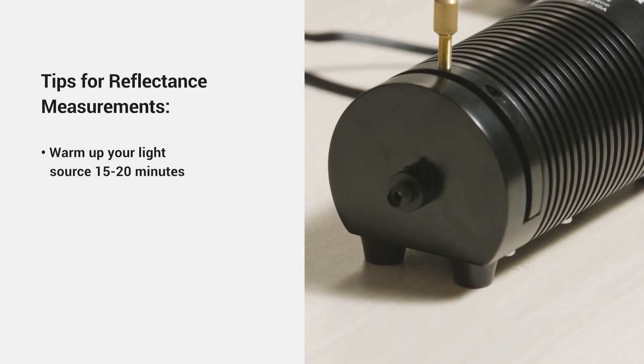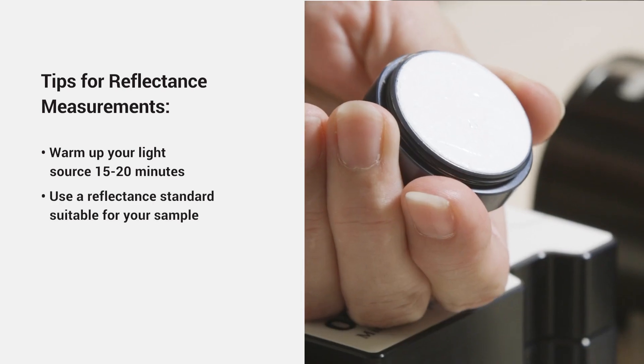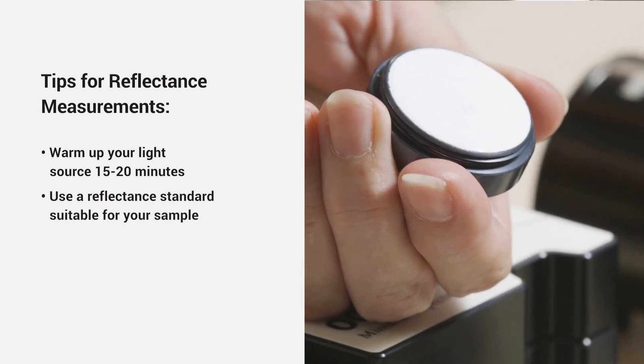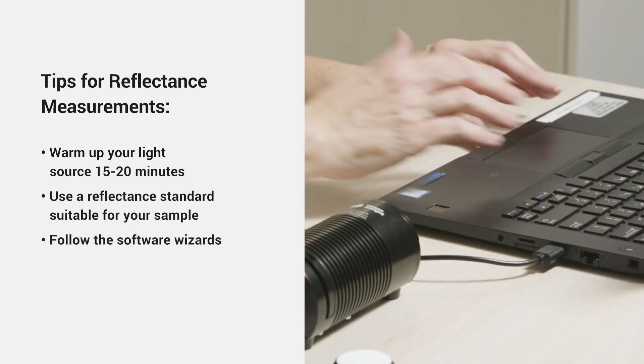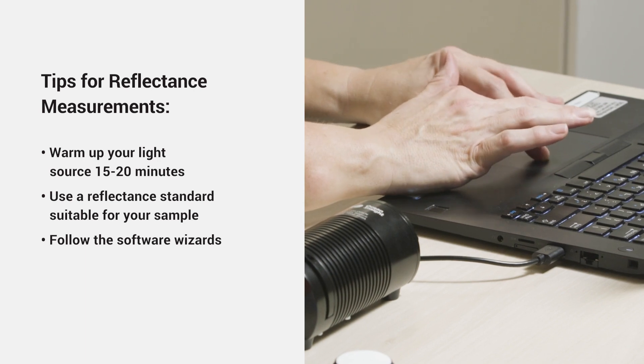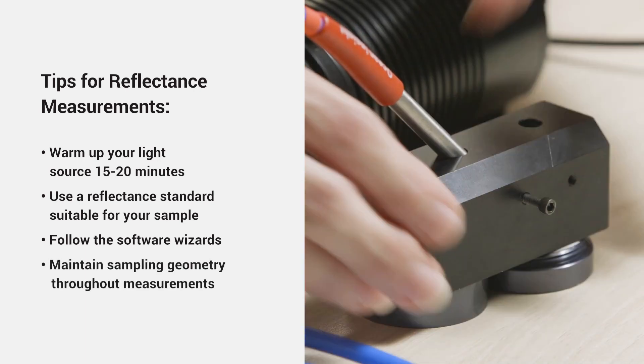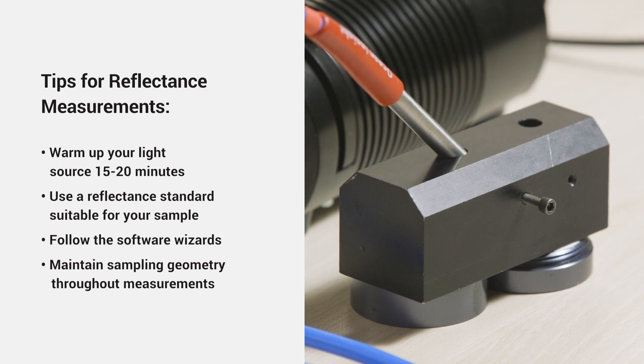So we covered setting up the software. Don't forget to warm up your light source for 15 to 20 minutes. We've talked about measuring your reference, measuring your dark, getting into reflectance mode. And in this case, we took it a step further and actually went into a color processing mode to get quantitative color.